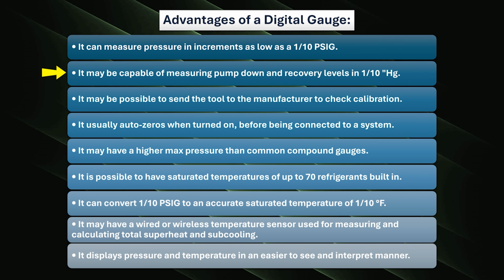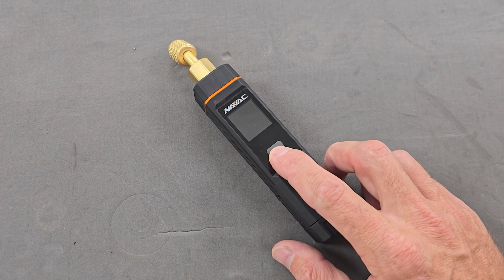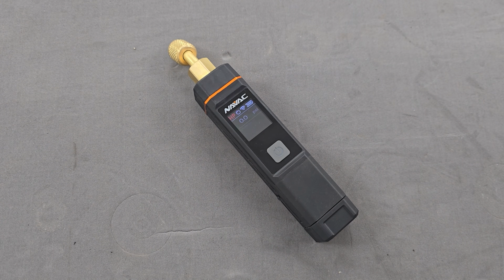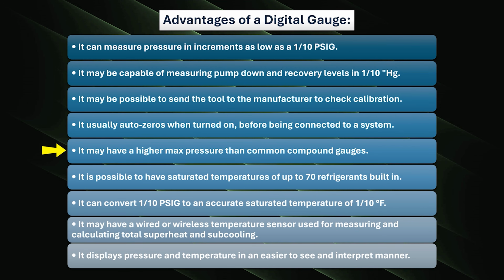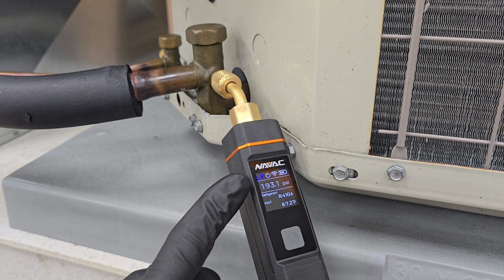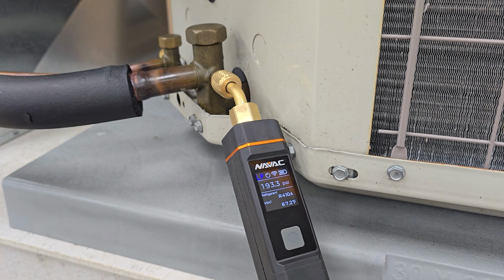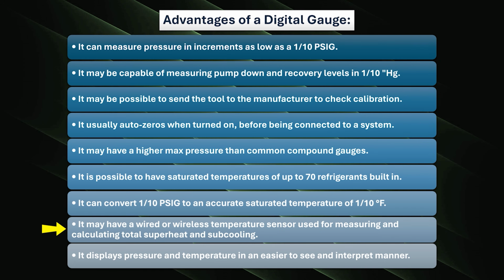It may be capable of measuring pump down and recovery levels in 1/10 inch Hg. It may be possible to send a tool to the manufacturer to check calibration. It usually auto zeros when turned on before being connected to a system. It may have a higher max pressure than common compound gauges. It is possible to have saturated temperatures of up to 70 refrigerants built in. It can convert 1/10 of a psig to an accurate saturated temperature of 1/10 of a degree Fahrenheit. It may have a wired or wireless temperature sensor used for measuring and calculating total superheat and subcooling.